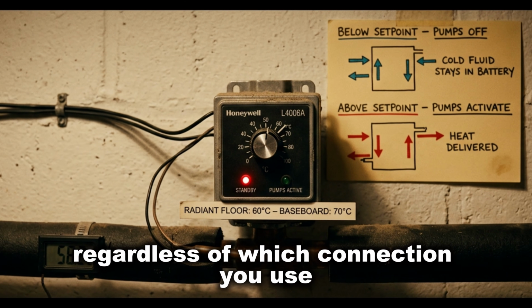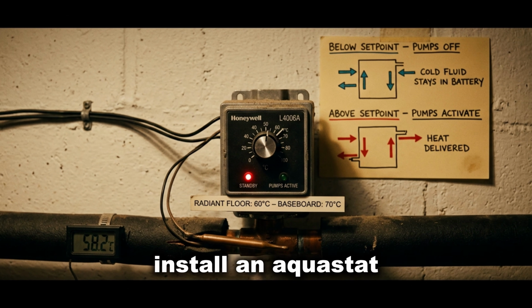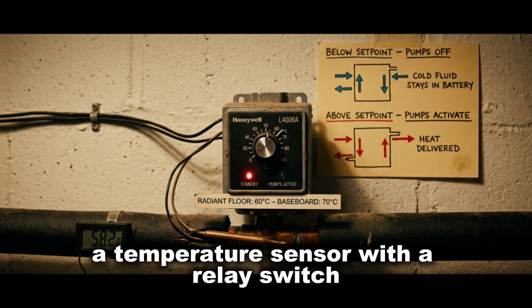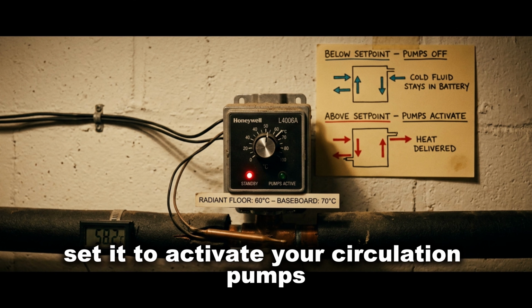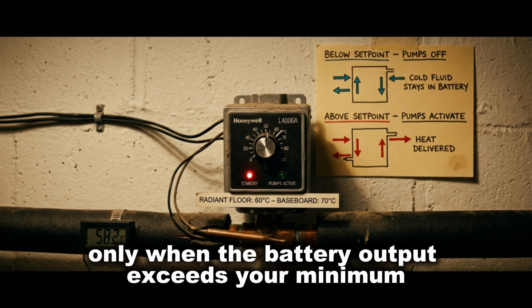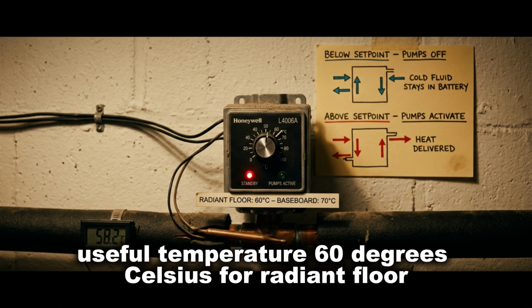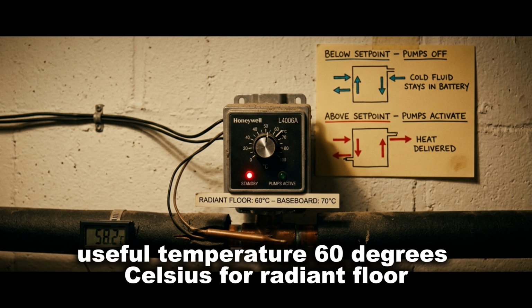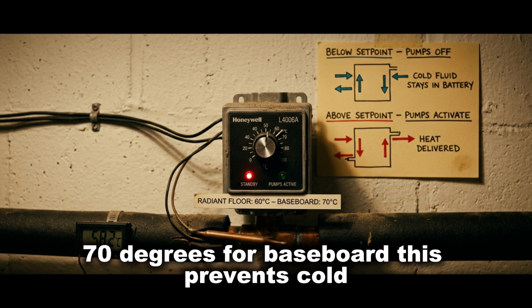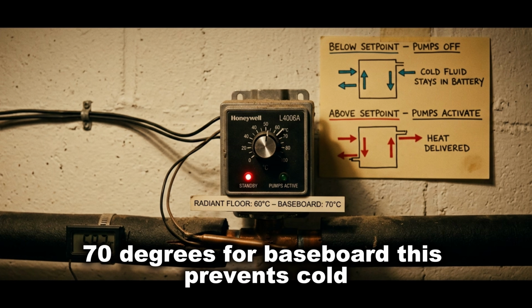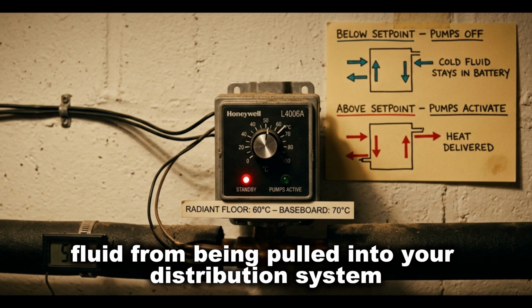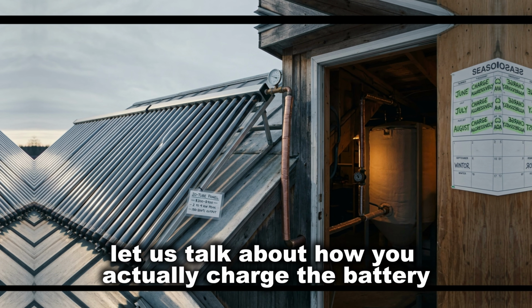Regardless of which connection you use, install an aquastat, a temperature sensor with a relay switch, on your sand battery output pipe. Set it to activate your circulation pumps only when the battery output exceeds your minimum useful temperature, 60 degrees Celsius for radiant floor, 70 degrees for baseboard. This prevents cold fluid from being pulled into your distribution system when the battery runs low. Now let us talk about how you actually charge the battery.